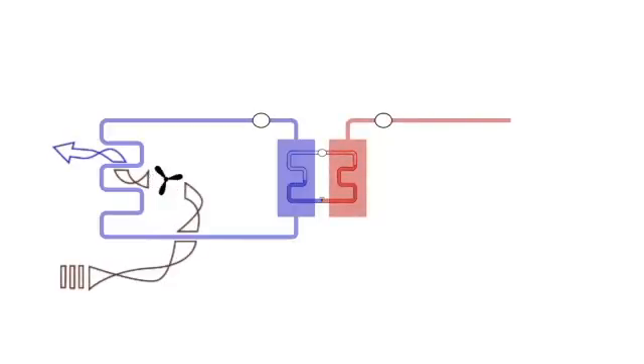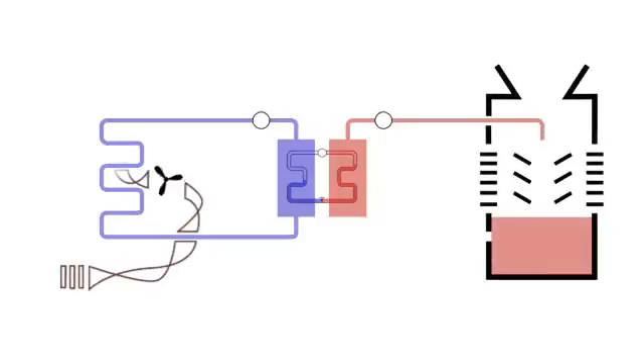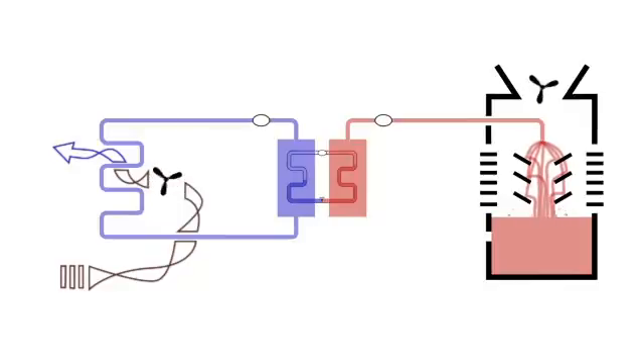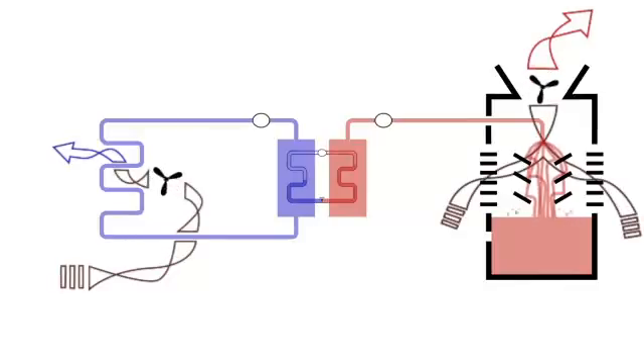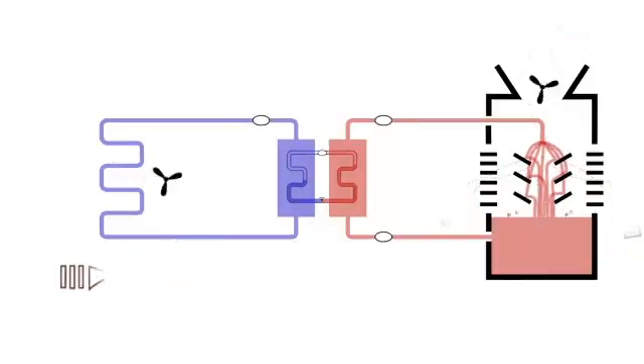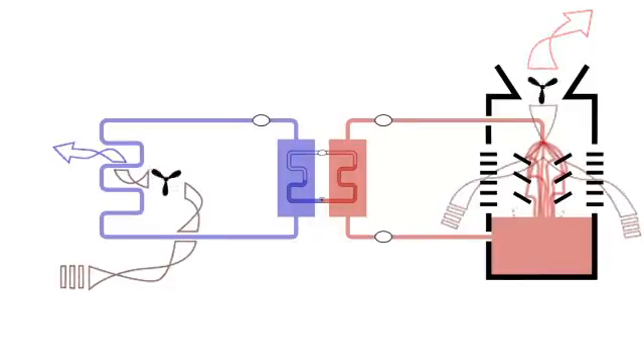This condenser water is pumped from the condenser to a cooling tower, and water is allowed to cascade over a series of baffles, where the water is cooled by the outside air. When needed, an impeller fan can assist airflow across the cascading water. Some of the water evaporates and is replaced with new water, but most of it falls to a pool, where it is pumped back to the condenser. This distribution network using water is complicated, but not exceptionally complex.